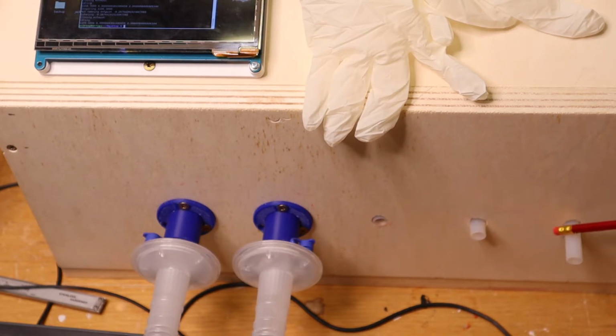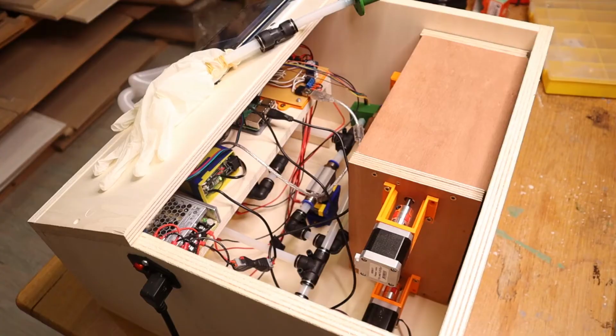And then on the right here we have 2 ports for oxygen and air, and these will be mixed in the appropriate ratio inside the device to deliver the mixed gas to the patient. Looking at the unit from the side now, here we have the power input, so currently I'm supplying it with 230 volts AC. And then looking inside of the unit, we can see 3 different sections to the device.